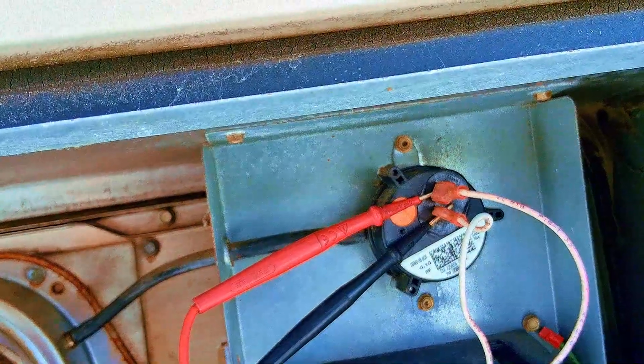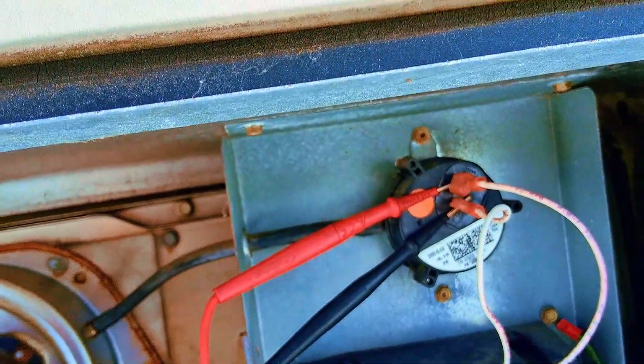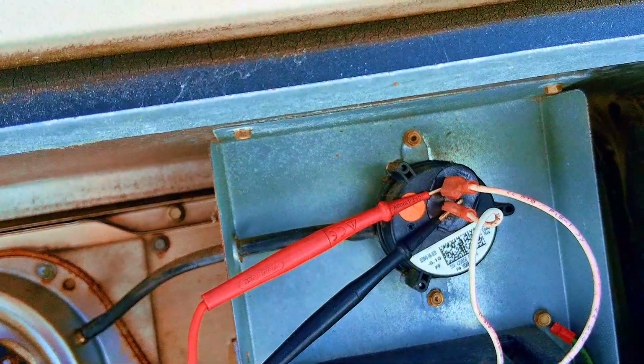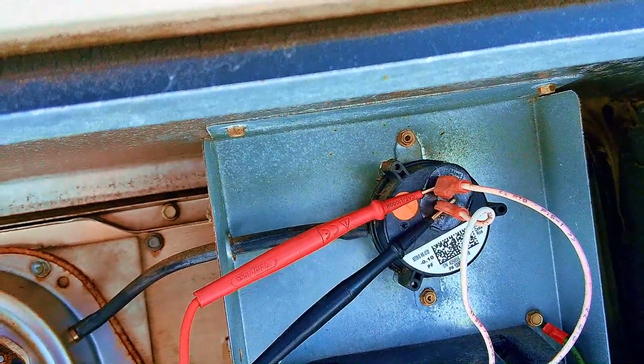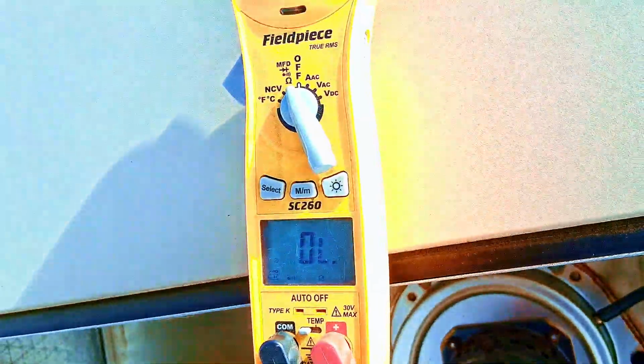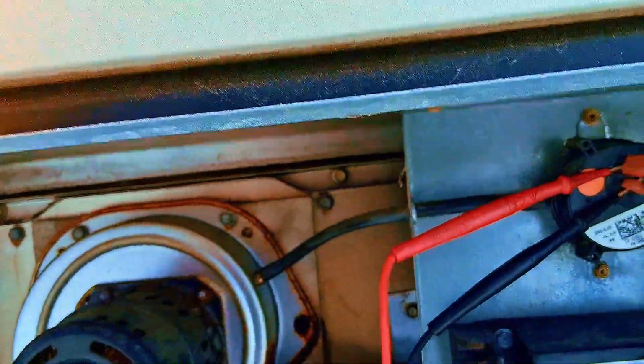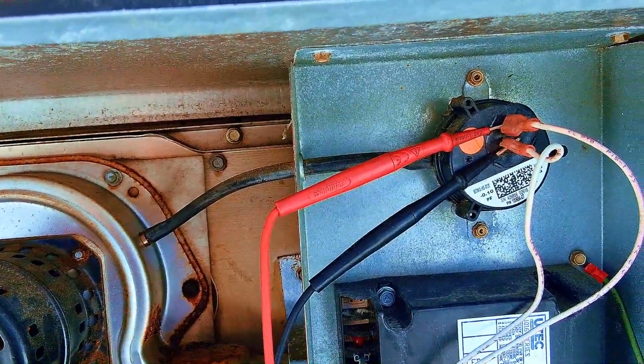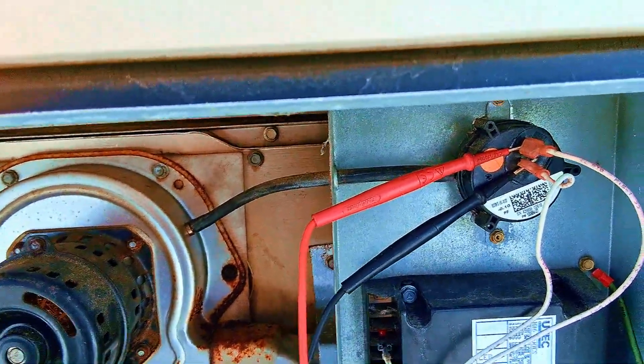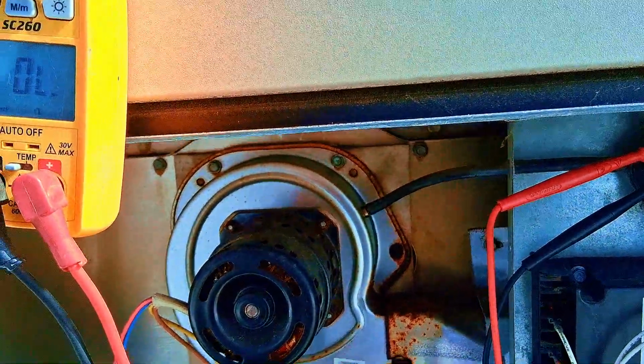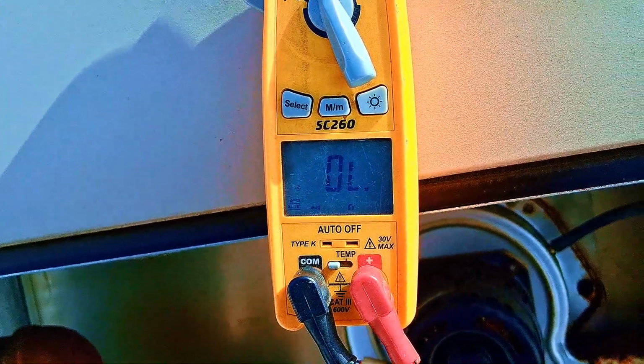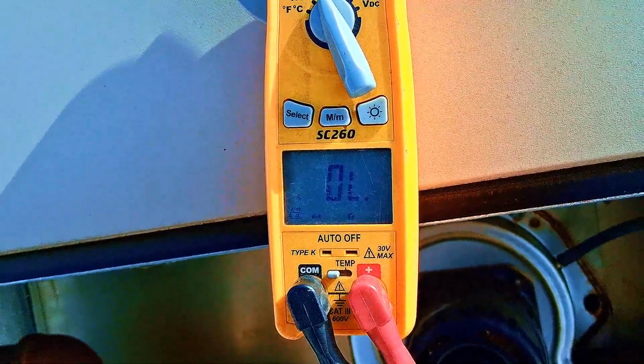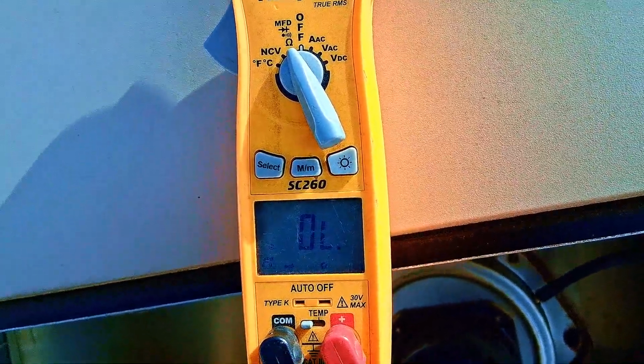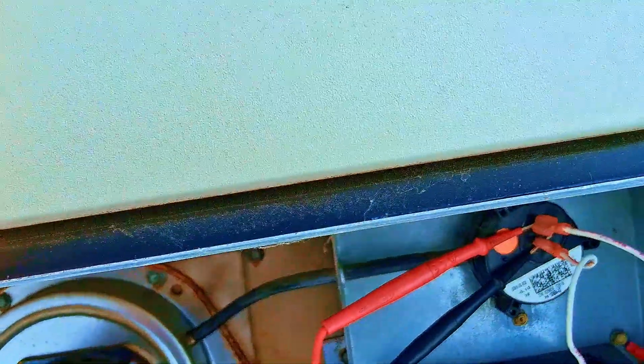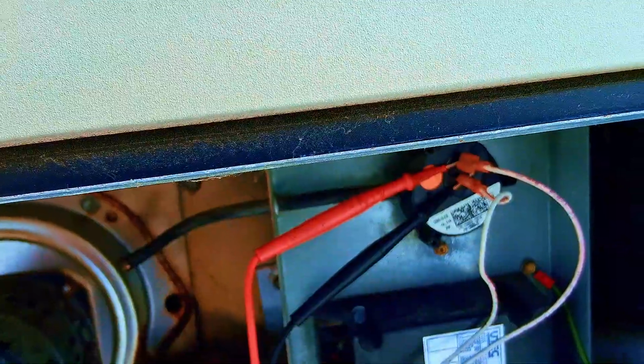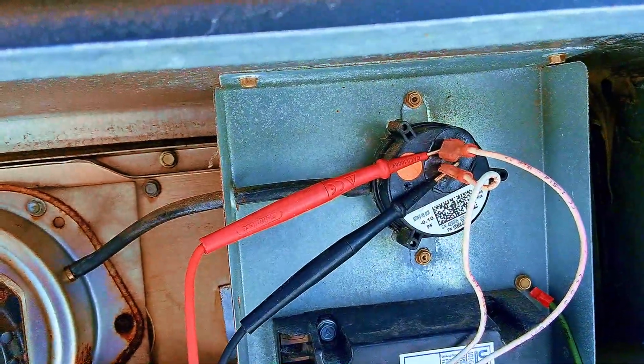So I'll pick it up as if the switch is closed, even though it's not a closed switch. It's just a signal that the board is sending over, getting ready to verify that the switch is open before it starts to heat. They said the way you test that is turn the unit off and do it. As you see right now, I don't have it calling for heat and it's OL. But as soon as I call for heat, it'll jump to reading continuity even when the inducer's not running. So that's how you can tell if the switch is bad or not. So I don't think I have a bad switch.